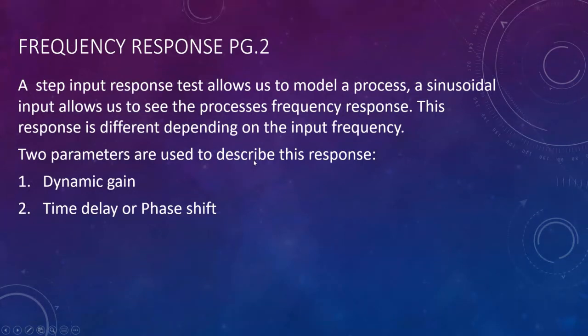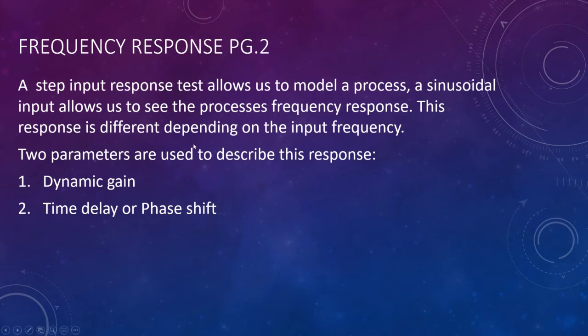A step input response test allows us to model a process — we've done these in earlier ILMs to find T1 times, dead times, and overall gains. Here we use a sinusoidal shaped input to see the process's frequency response. The response differs depending on the input frequency. Two parameters describe this response: dynamic gain (change in output over input) and time delay or phase shift — the difference between when the change occurred and when the output reacted.